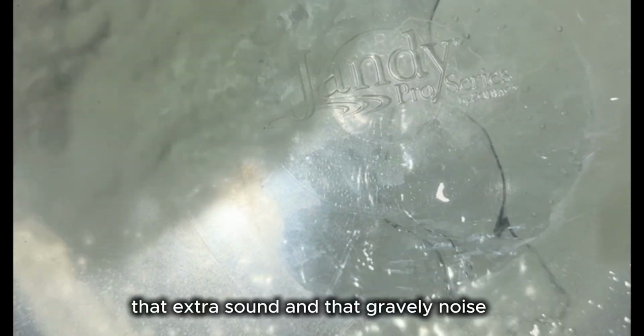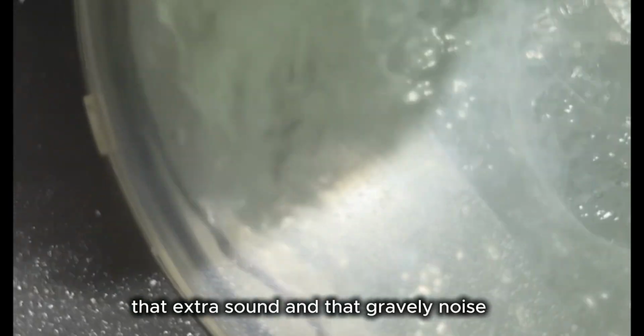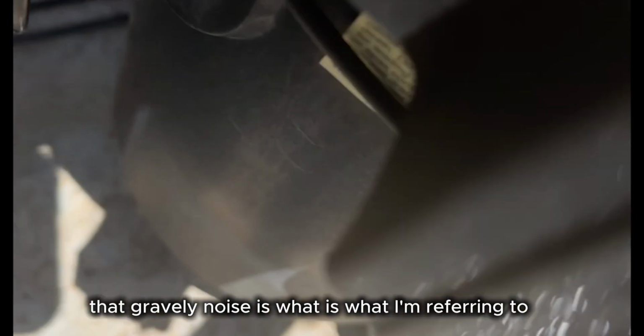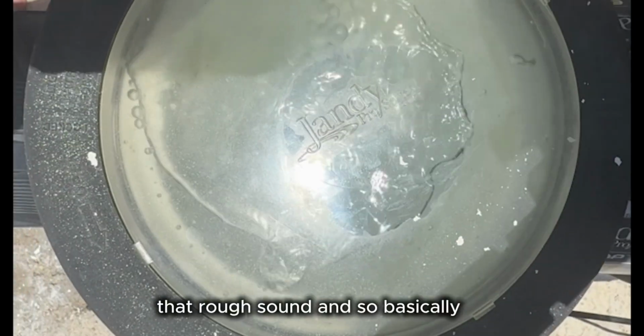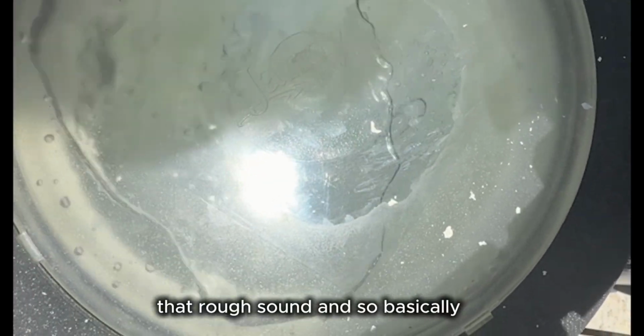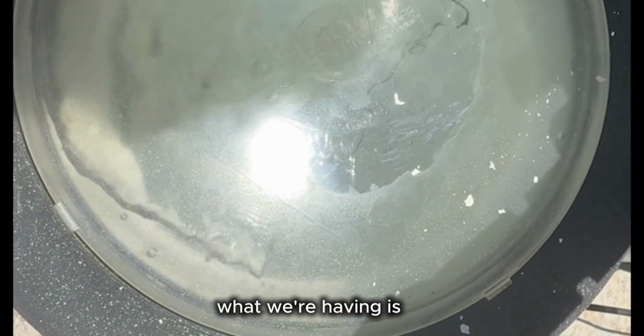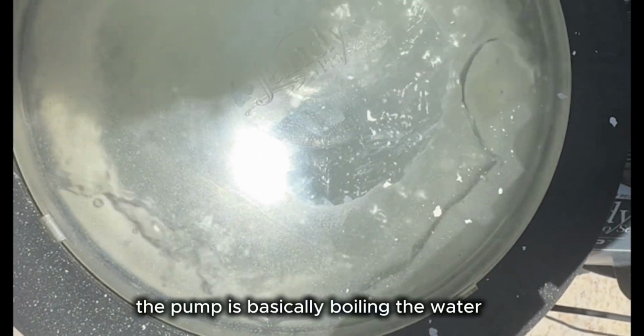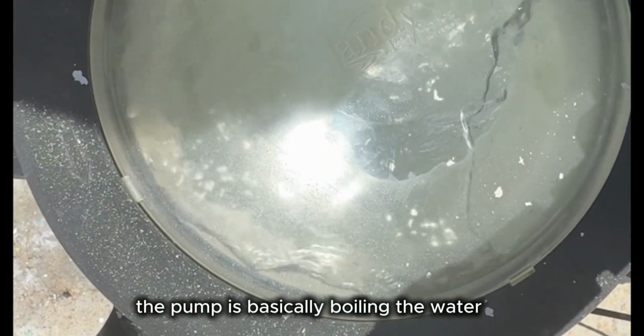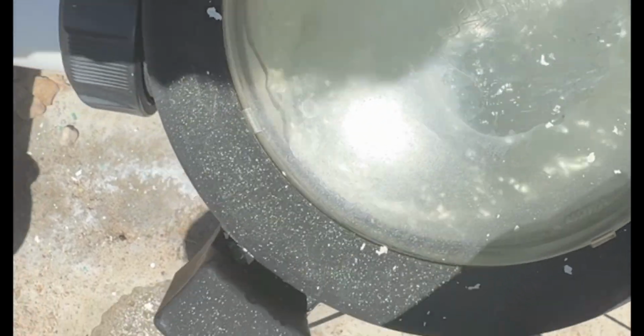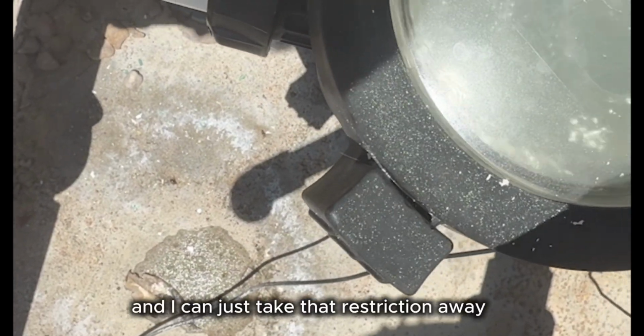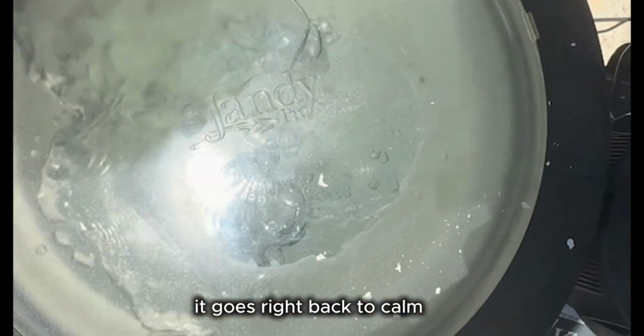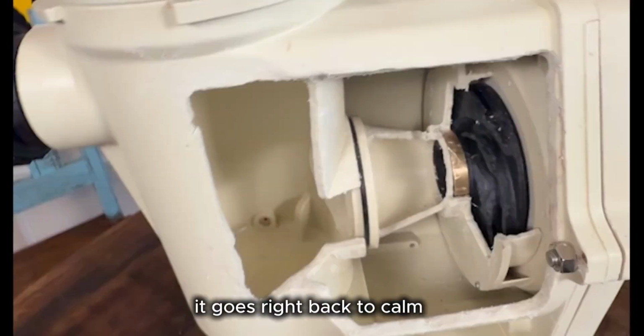Notice that extra sound and that gravelly noise. That gravelly noise is what I'm referring to, that rough sound. Basically, the pump is boiling the water because of the negative pressure. And I can just take that restriction away, and it goes right back to calm.